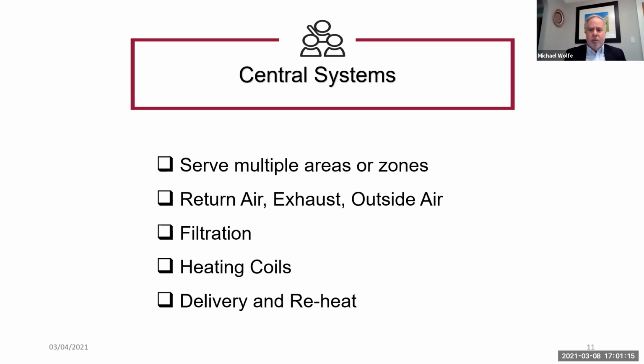Anything else on central systems before we jump into the unit ventilators? Well, I'd just like to say that the outside air that we talked about, that it pulls in, those settings have a minimum amount of outside air that we're required by law to bring into our buildings, and that's existed way before COVID. So that's always been a requirement of these systems, that they do bring in outside air all the time. And then as temperatures increase or CO2 increases inside the building, that will modulate to even more outside air. So we can bring in a lot of outside air in these systems.